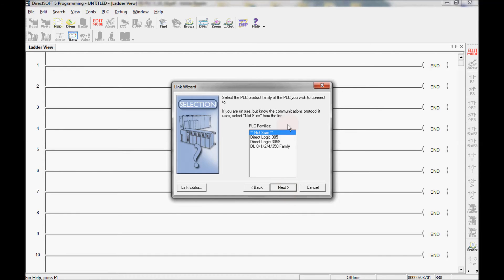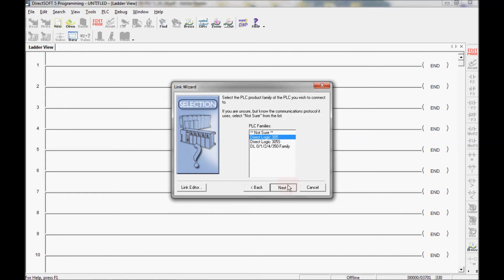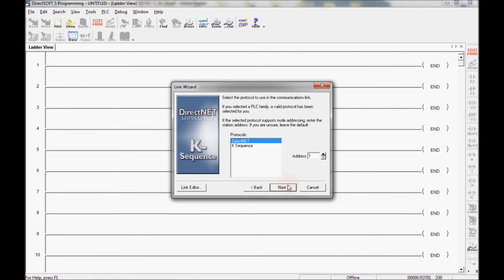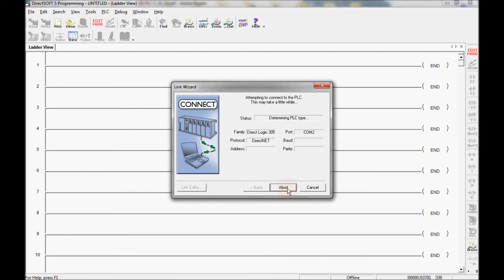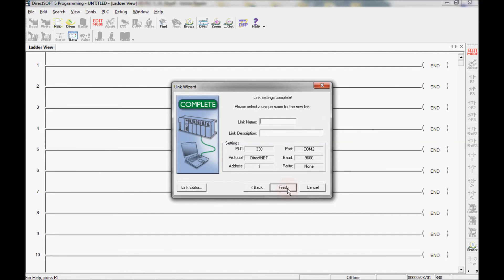I'll make sure that COM port 2 is highlighted and press next. I'll use the link wizard to configure this for me. Under PLC family I can either use not sure or select Direct Logic 305 then select next. The protocol I want to use is DirectNet and address 1, select next.